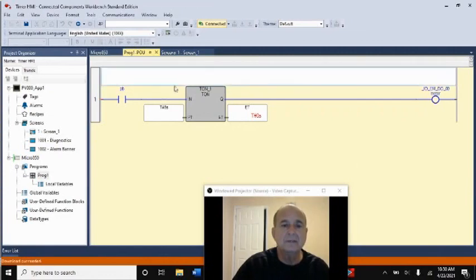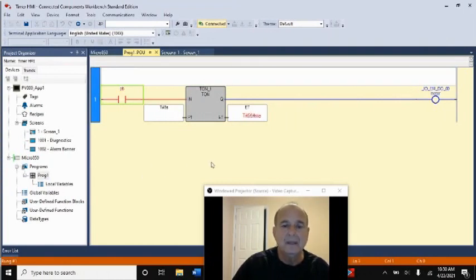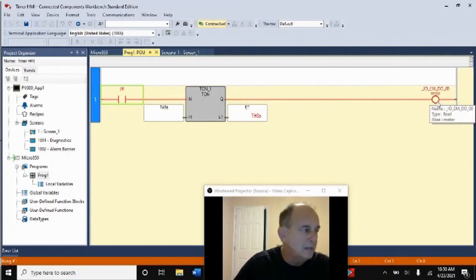And we can go ahead and check this on the PLC first. I'll go ahead and right click and toggle that. And let's see if it starts timing. It does. You can see, and then when it gets to, I believe I put in 6 seconds, the motor comes on and you can see that it's highlighted over there. Okay, and I'll go ahead and stop that.